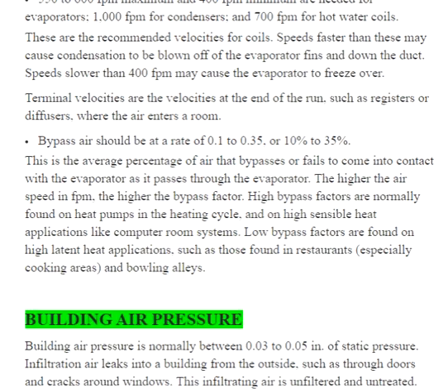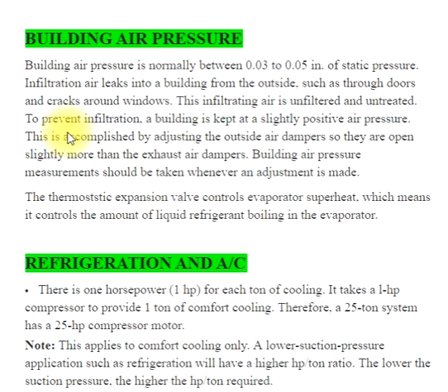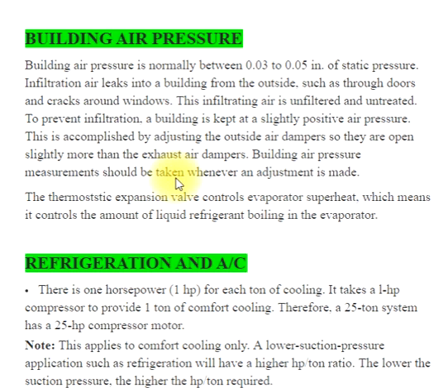Building air pressure is normally between 0.03 to 0.05 inches of static pressure. Infiltration air leaks into a building from the outside, such as through doors and cracks around windows, and this infiltrating air is unfiltered and untreated. To prevent infiltration, a building is kept at a slightly positive air pressure by adjusting the outside air dampers so they are open slightly more than the exhaust air dampers. Building air pressure measurements should be taken whenever an adjustment is made.